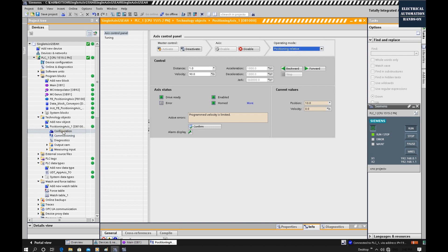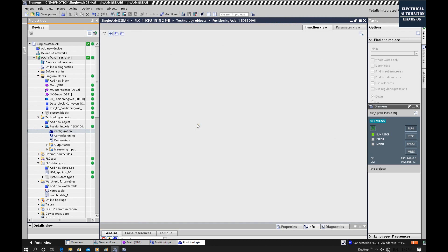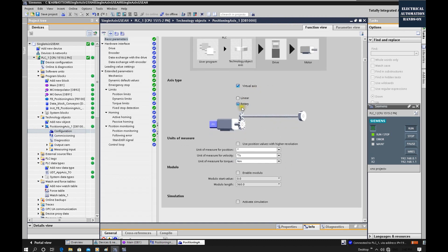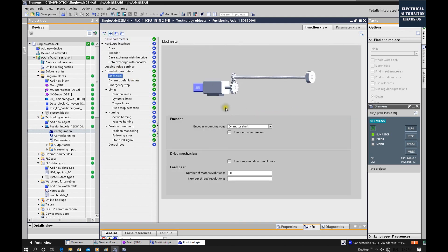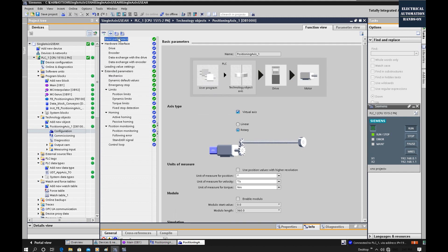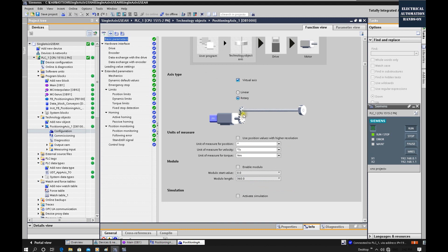We need to verify in our configuration. If we quickly recall, we need to verify this setting. Now we are setting as rotary. The motor is 10 revolutions and our load will run one revolution. Keep in mind, the speed represents the encoder, and because this encoder is on the shaft, it represents the speed of the motor. The velocity represents our load. In this setting, our load unit is degree per second, but the speed of the motor is degree per minute.